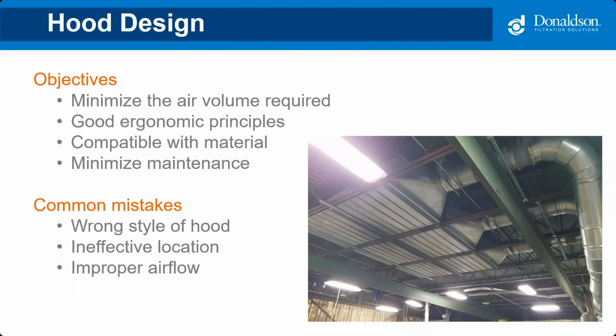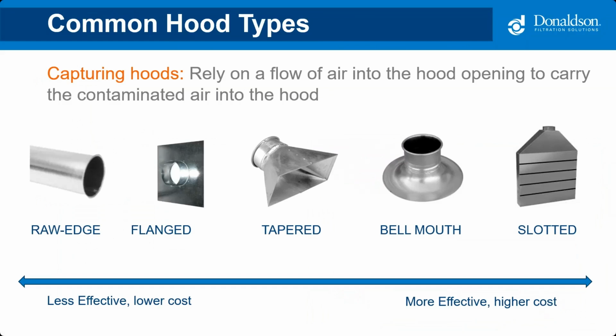So when it comes to assessing an existing system, a few common mistakes that we see are the wrong style of hood is being used, the hood is not located in an effective position, or you have inadequate airflow at the hood. In my experience with battery manufacturing, the dust collection system is often connected to a series of machines with built-in hoods or a simple dust port connection that only requires an airflow and static pressure for design. However, there are times when a hood is required, especially in the mixing and weighing operations where materials are exposed.